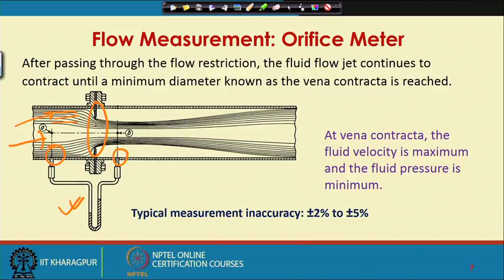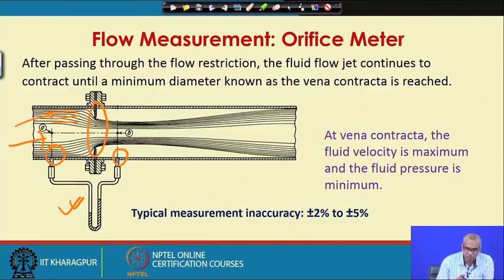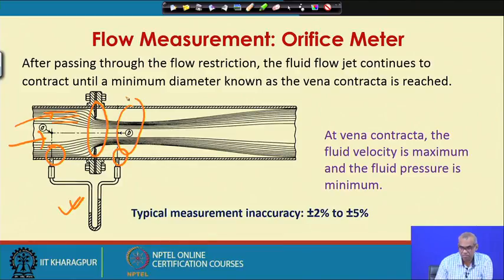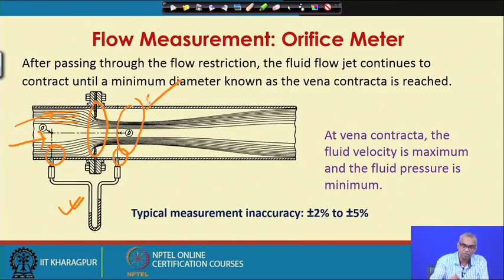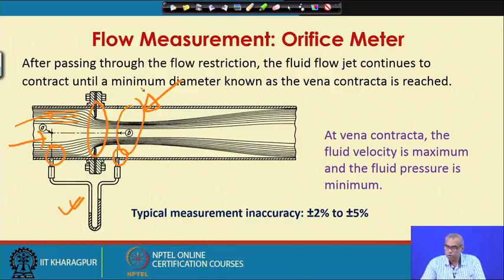As the fluid approaches the flow restriction, the flow jet contracts, but it continues to contract even after leaving the orifice to some extent, and then again it expands. After passing through the flow restriction, the fluid flow jet continues to contract until a minimum diameter known as vena contracta is reached. At vena contracta, the fluid velocity is maximum and the fluid pressure is minimum.